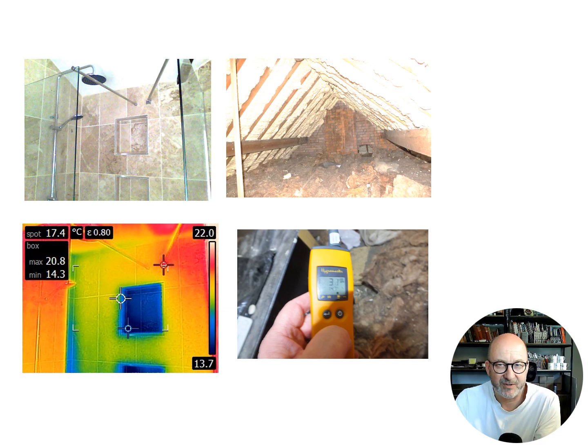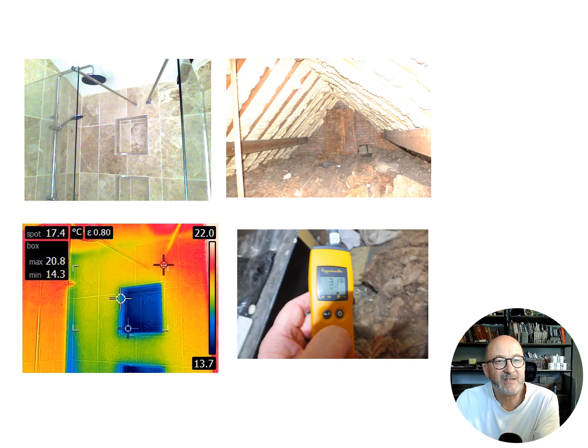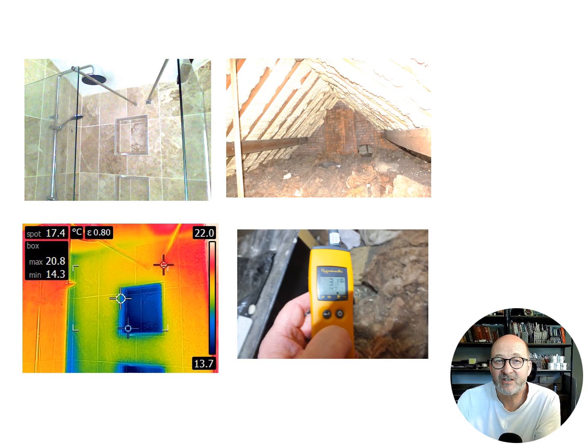Here are some examples. You can see a thermal image of an alcove in a shower cubicle with a large blue cold spot, because it is an outside wall and the alcove is built into the thickness. Predicting condensation won't occur in principle when additional materials are added — such as spray foams — can be equally misleading. The length and severity of winter and the ability of materials to safely store and later expel moisture are important factors in determining where moisture will actually occur.